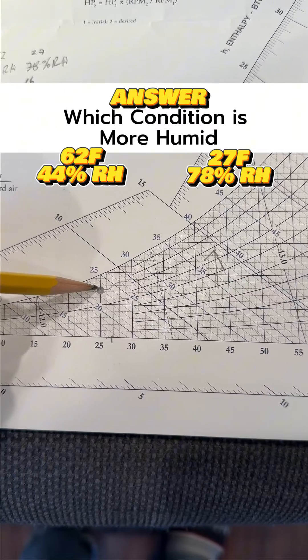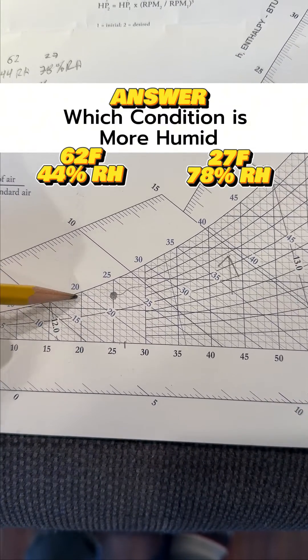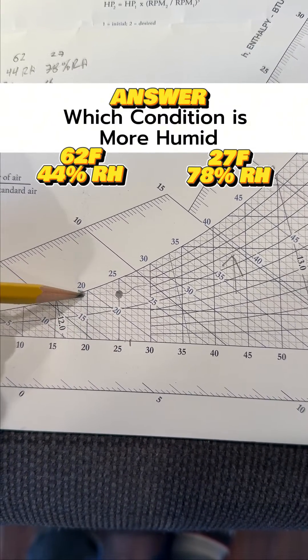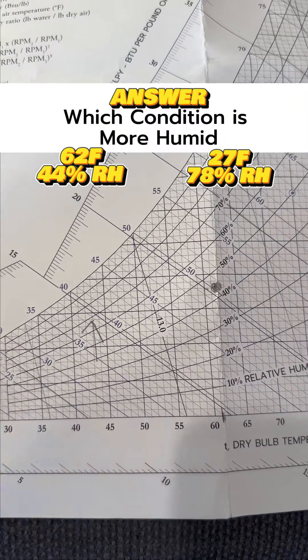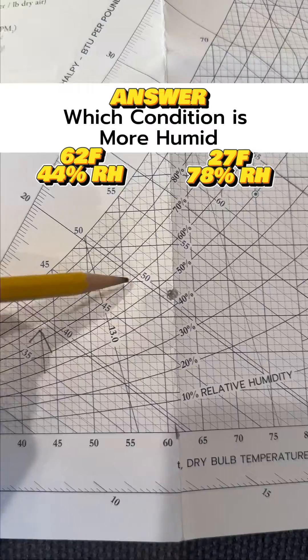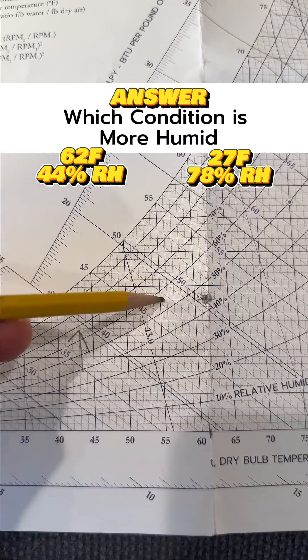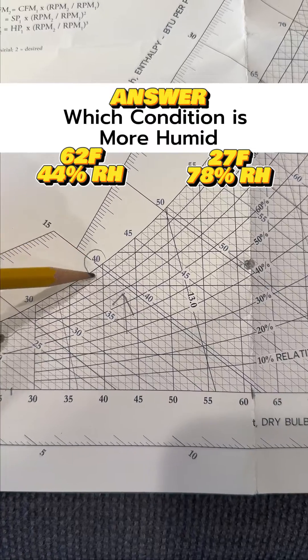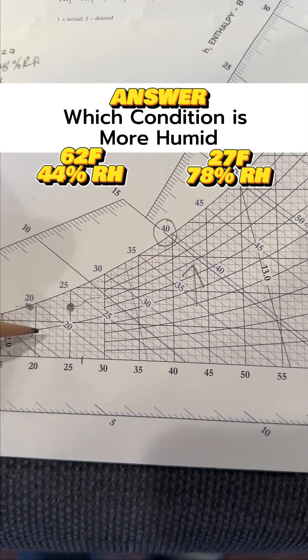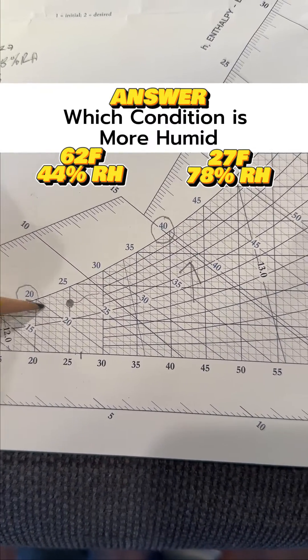And you can see the dew point, which we didn't really talk about, of this air is around here, which is about 19 degrees, maybe 20 degrees. The dew point of this condition here, if we go to the left, is about 40 degrees. So dew point is a good indicator of the amount of moisture in the air as well.